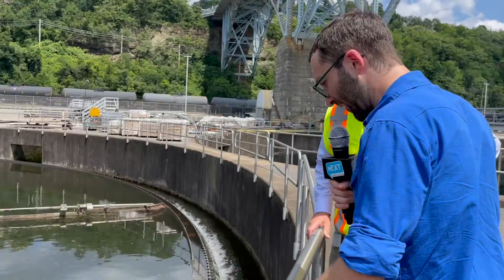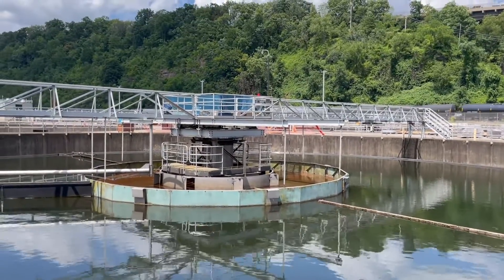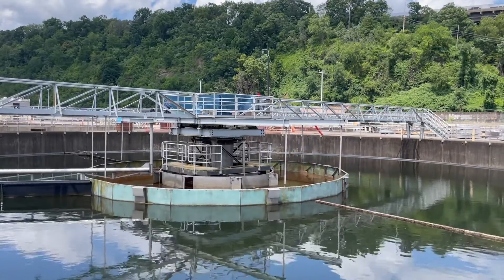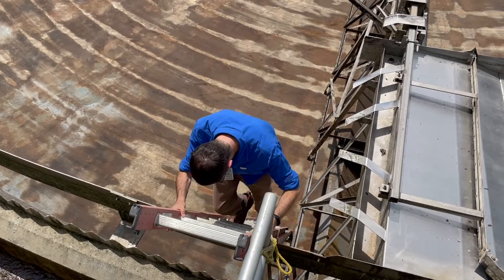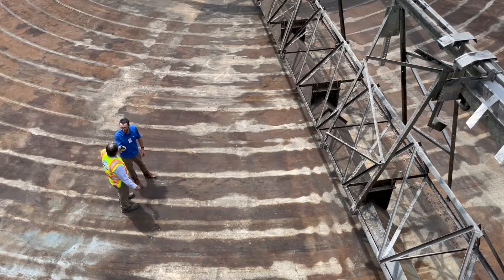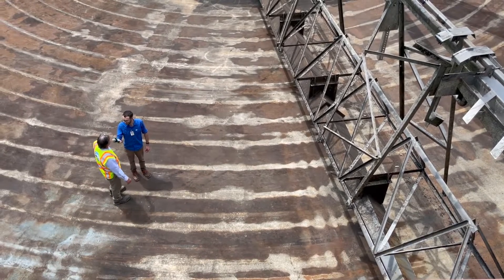So this is looking a lot less brown over here. That water that we just saw is going into the center chamber. When you look in the middle of this clarifier, that's where the very discolored wastewater and microorganisms enter into this tank. It stays in here for about two hours, where the discolored material simply settles out at the bottom. If you look underneath that big metal structure, you see small openings — that's where we vacuum up all the bugs, suck them off the bottom, and pump them back to the aeration basin to reseed the process itself. No chemical addition — a very tried and true clarifier design.